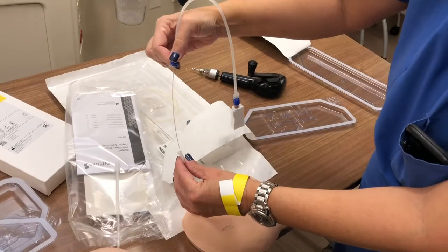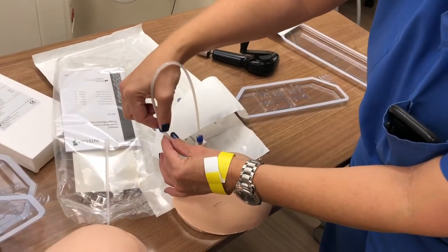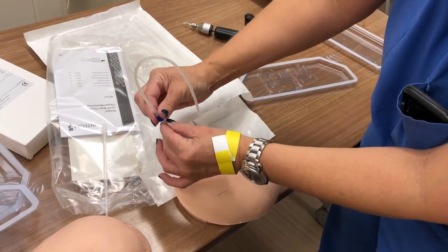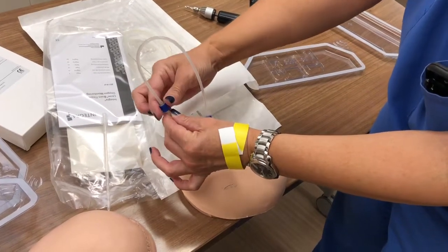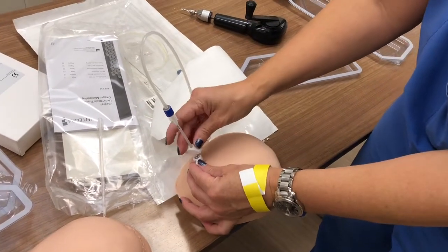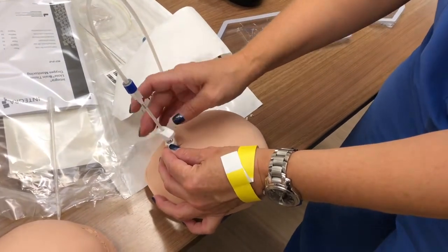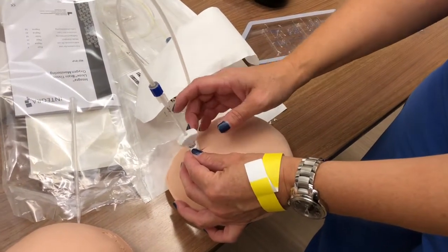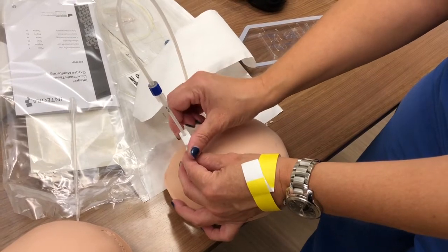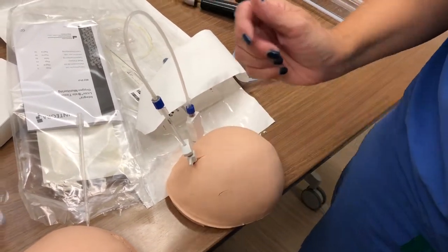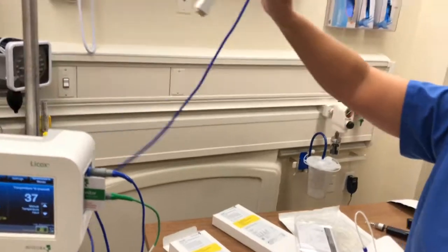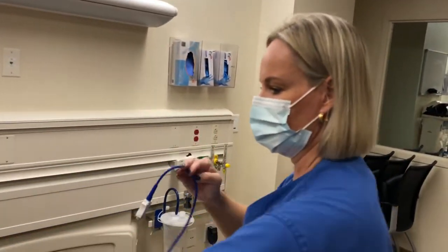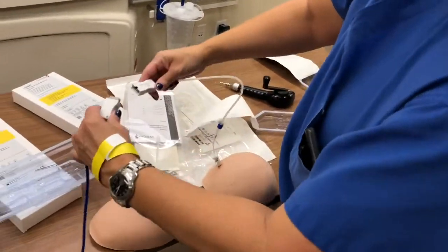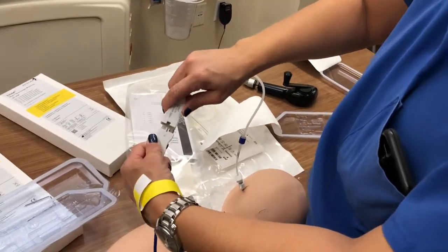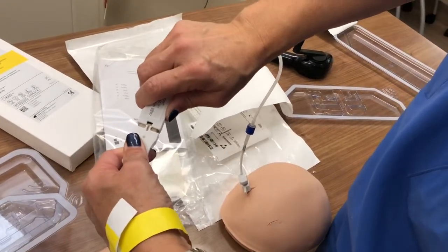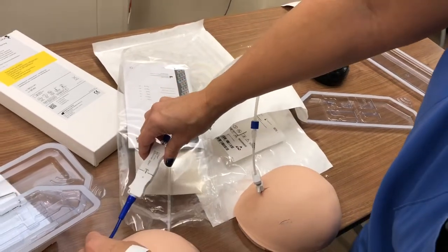I'm going to insert this down here, and then this is simply going to fasten down like so. Once I've tightened down to the actual port, then I'm able to tighten the wing nut. The wing nut is never tightened until the end of everything is being inserted, and it's finger tight, and that's plenty tight there. You're then going to take the end of your cable for the Licox monitor, and you are going to connect as such. It has a little groove there, so you kind of know that it's going to go into there. There we are.